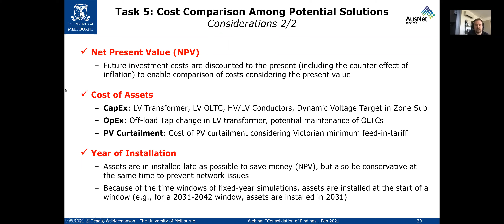So the next window was 40%. We say, okay, let's replace the transformers the year after it hits 40%. Let's say that's 2030, so we'll install them in 2031 so that by the time we get to 2040 we know it's going to be okay. This way you get the maximum discount by installing them as late as you can. The earlier you install them, the more it costs. So you want to install as late as you can get away with, but still be conservative enough that we replace these assets before problems occur. That's a key aspect to think about: when you need to install these assets.